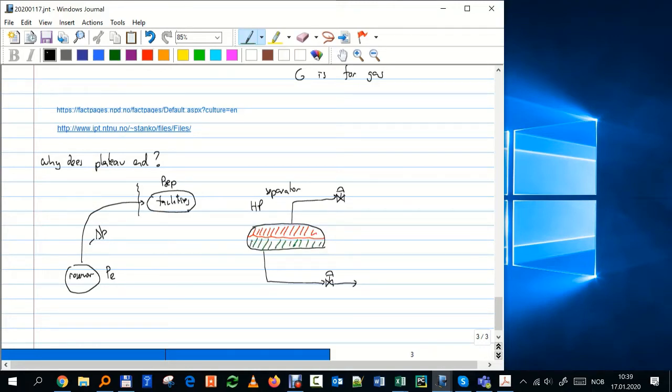First, you have a level controller. Let's say, in a very simplistic way, it's a floater. You want to make sure that the level is at a particular height. If it goes too high, what might happen? You might start getting liquid into this line, which is not good. I have compressors and all kinds of things that depend on the phase being primarily gas. So this controller is controlling this valve and making sure that the level is within a range.